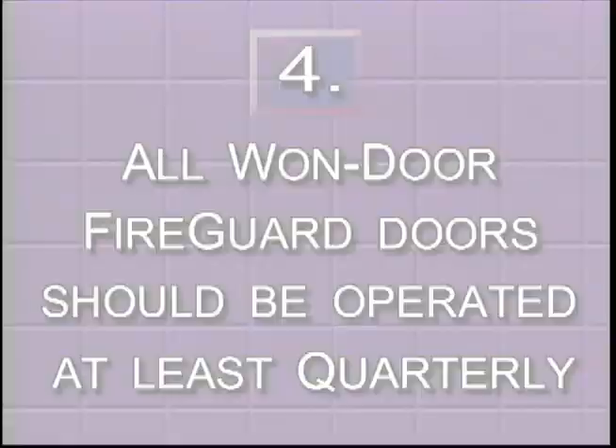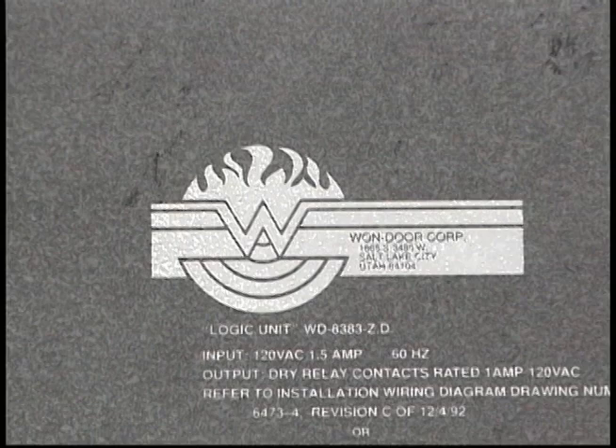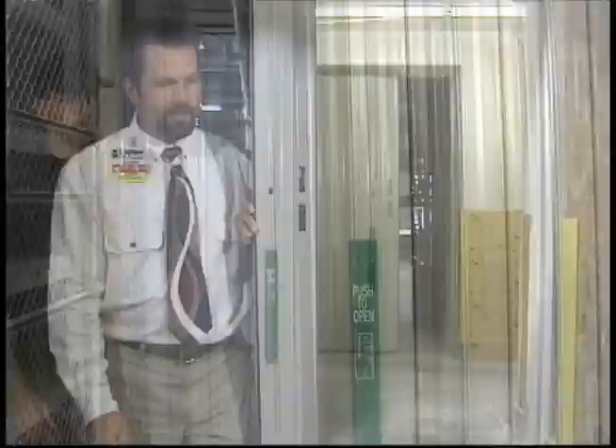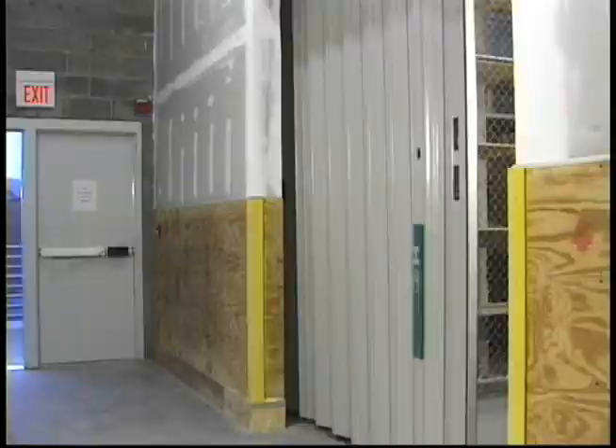Just a reminder — we suggest that all Won-Door FireGuard doors be operated at least quarterly. The Won-Door FireGuard system is the only fire door assembly which is completely electronically supervised. The microprocessor located in the control box receives various inputs from integral door components. This monitoring is continuous, occurring approximately three times per second. If for some reason a fault condition occurs, an audible signal will be communicated from an alarm located on the control box. Let's briefly examine a few of the most common fault conditions.